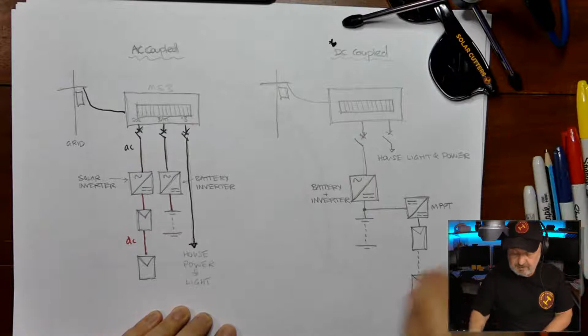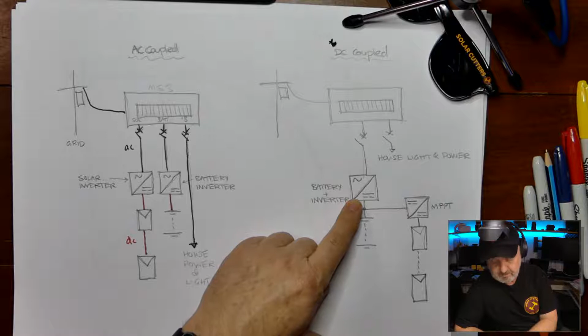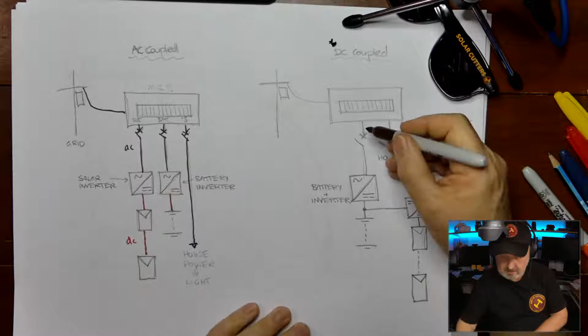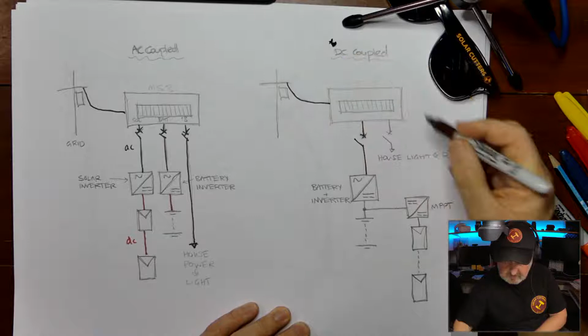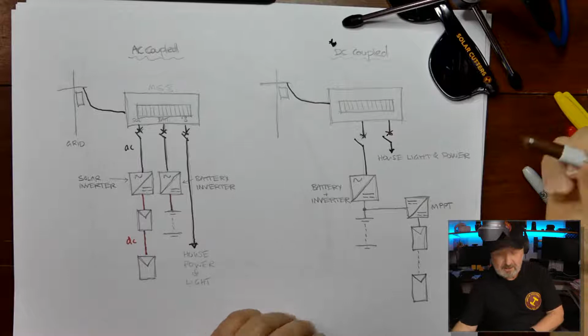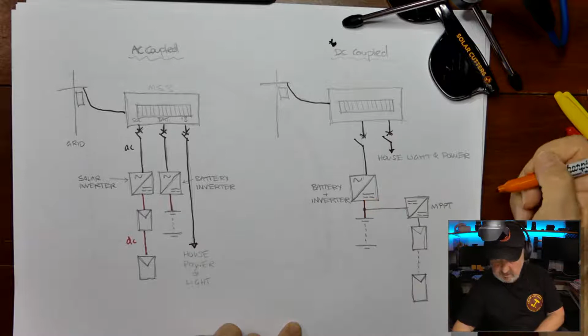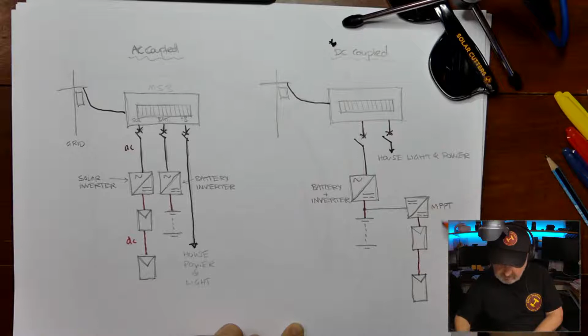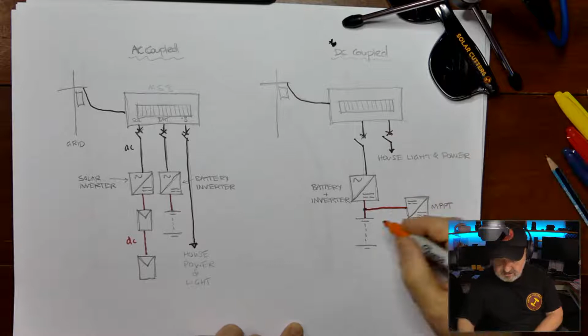So that's AC coupling. Moving over to DC coupling by contrast, here we've got a battery inverter, connected by an AC circuit to the switchboard, and we've got some light and power for the home here. So the DC side here is connected to the battery, but the way that the DC PV power gets to the battery is through a dedicated DC connection. So it's coupled on the DC side.